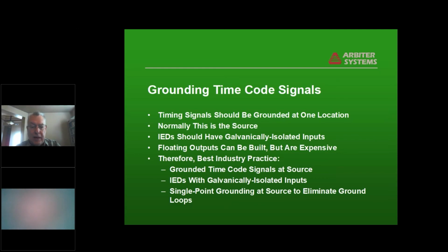So the best industry practice is to ground the time code signals at the source, use IEDs with galvanically isolated inputs, which can be a transformer in the case of an IRIG modulated signal or opto-isolator or digital isolator in the case of a digital signal, 1 PPS or IRIG-B. And we use single point grounding at the source to eliminate ground loops and provide a safety ground.